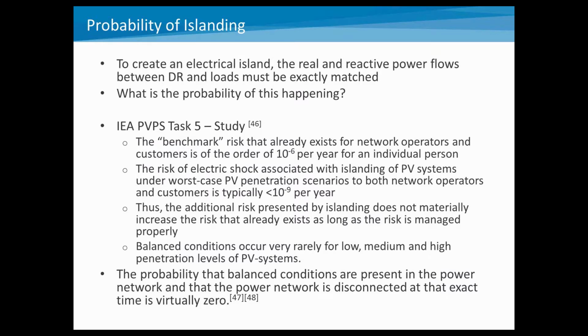So the outputs of this particular study basically said that there's a benchmark risk that already exists for network operators and customers, on the order of 10 to the minus 6 for any individual person. And looking specifically at the risk of electrical shock associated with islands under worst case PV penetration scenarios, it was typically less than 10 to the negative 9 per year. So that's a number of orders of magnitude difference, because you have to maintain this matched real and reactive power case.